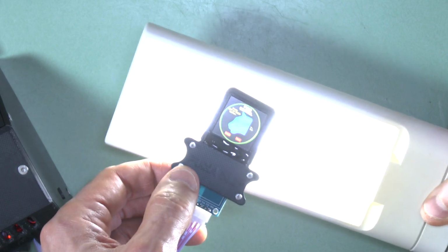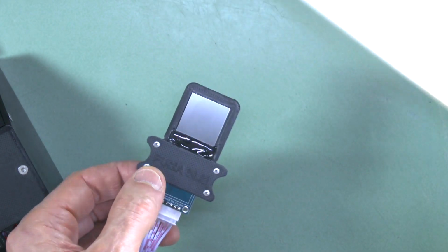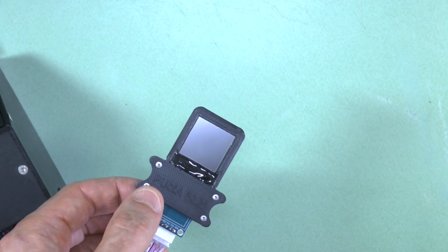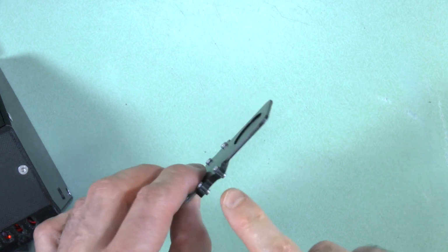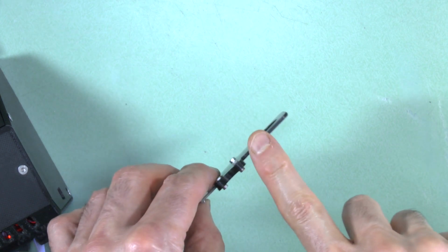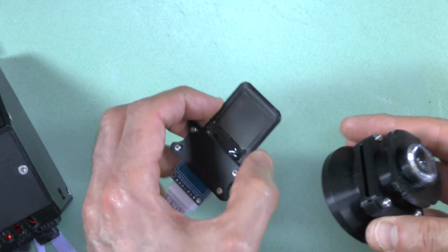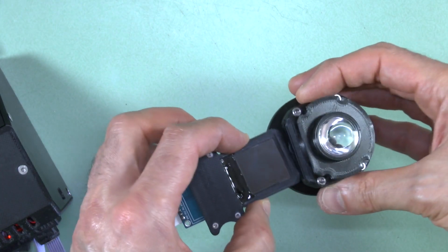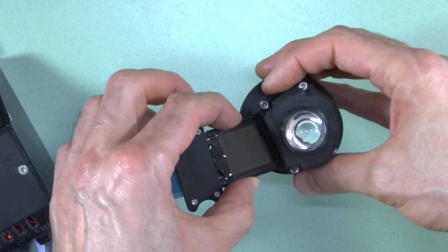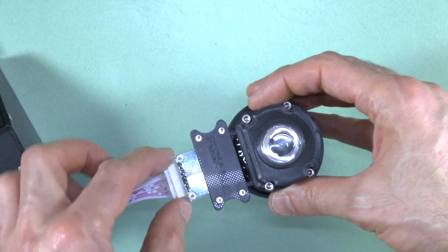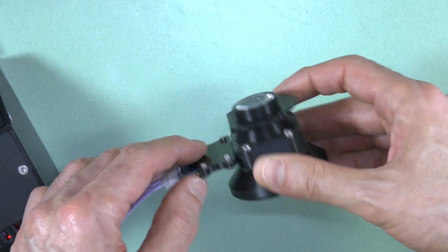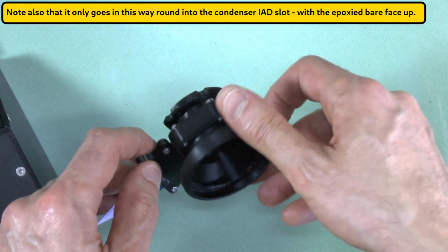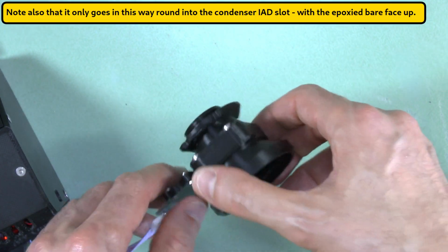Always take care when inserting or removing the SLM from a filter slot not to put bending pressure between the filter handle and the filter slider. I tend to hold the SLM by the sides of the slider, not the handle, when inserting it most of the way, and only use the handle to push it in the final amount till it clicks in place. If you feel undue resistance, stop and investigate why.